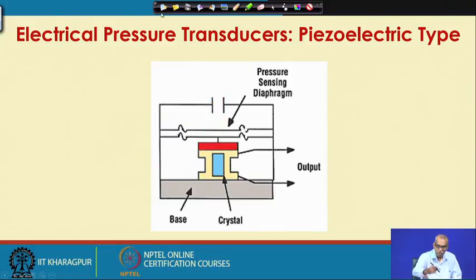So, you make use of a diaphragm, let the pressure act on the diaphragm, a force will be developed, and a piezoelectric crystal is connected to the diaphragm. So, as pressure is applied, the diaphragm applies a force on the piezoelectric crystal, and when the piezoelectric crystal senses force, a charge is accumulated on the surface. So, that is a piezoelectric property. We have talked about it when we talked about piezoelectric transducers. So, that way you can convert a diaphragm to an electrical pressure transducer, which makes use of piezoelectric crystals.